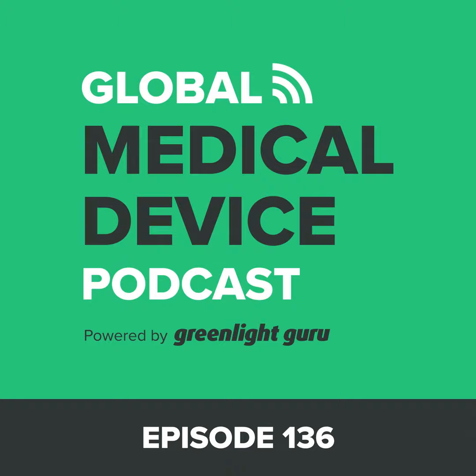Well, as I said earlier, I think if it does, it's going to be pretty minimal at best. I'll be brutally honest with you, John. I think what will reduce the review time a heck of a lot more is having a good pre-sub with the FDA in advance of any submission. And this is a topic that you and I have talked about before.